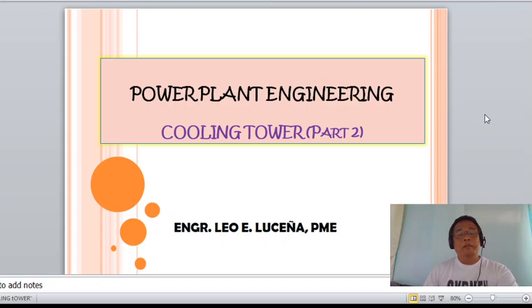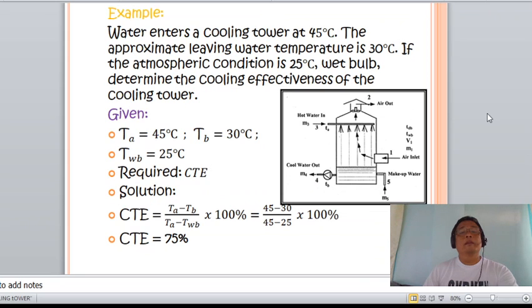So by this time, we'll now take up examples on how we are going to apply the definitions of cooling tower. Okay, so let us consider this. Water enters a cooling tower at 45 degrees Celsius. The approximate leaving water temperature is 30 degrees. If the atmospheric condition is 25 degrees wet bulb, determine the cooling effectiveness of the cooling tower. So when we say cooling tower effectiveness, we are referring to the efficiency of the cooling tower.